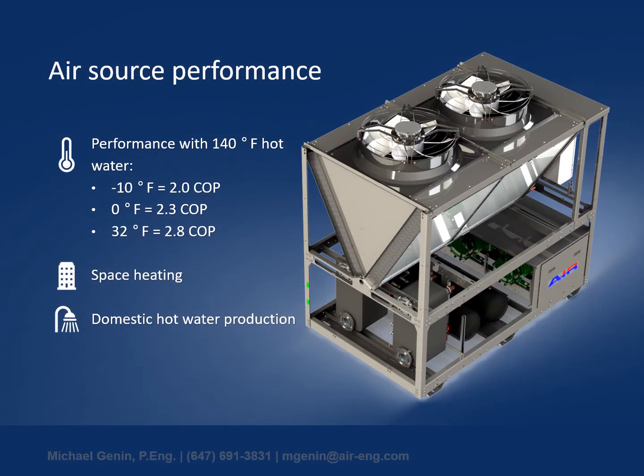Air source heat pumps have really become the talk of the town these days, and essentially what they are is what we think is a chiller, but in reverse. They're a refrigeration cycle, and just like every other refrigeration cycle, they move heat energy. In this case, they're moving heat energy from the ambient air and using it to generate hot water. And I've laid out a couple performance points there for an air source heat pump, making 140 degree hot water. With 140 degree hot water, you can achieve your space heating needs and achieve perhaps your domestic hot water production.